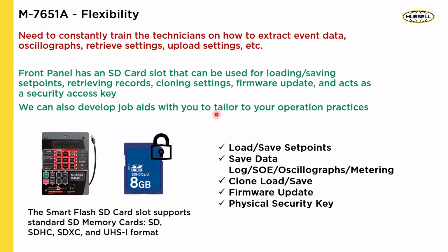The other challenge is there's a constant need to train your technicians on how to extract the event data, oscillography, to retrieve settings or upload settings, right? So the feature that we provide here is through an SD card. So in the front port, you have an SD card slot. Now that can be used for loading setpoints, saving setpoints. You could have the saving of the oscillography records, metering, data logs, right? You could clone, so you could copy settings out of this and put it in a different relay. You can update the firmware with this, and it also acts like a physical security key. So you know that you gave it to the right person, and the right person is going in and doing the job, and there's no other person who has access to it other than the person who has the SD card. Basically, that becomes your key.